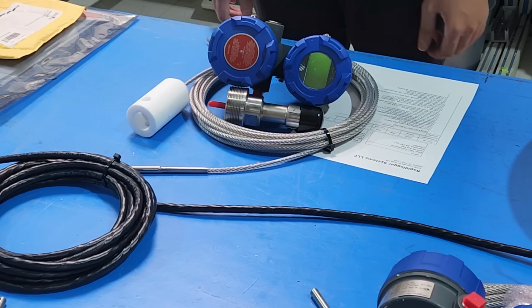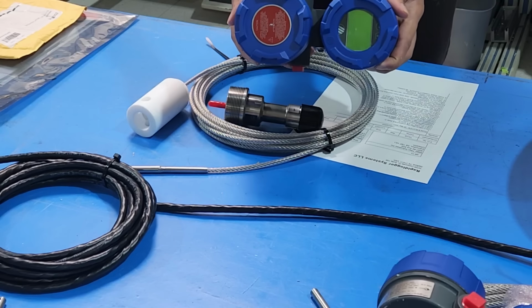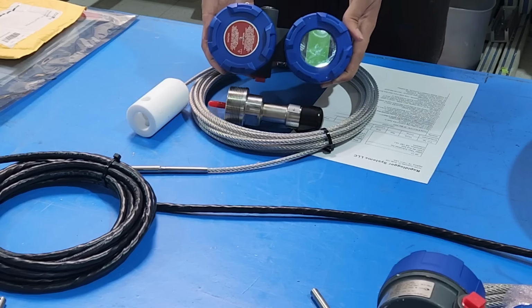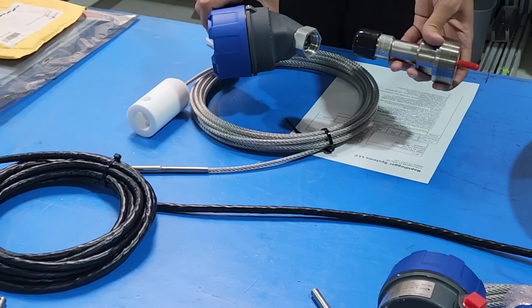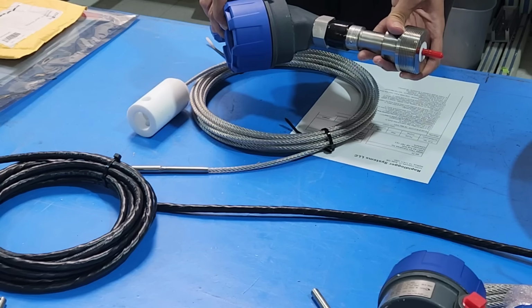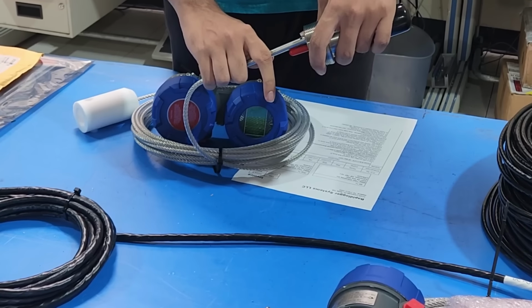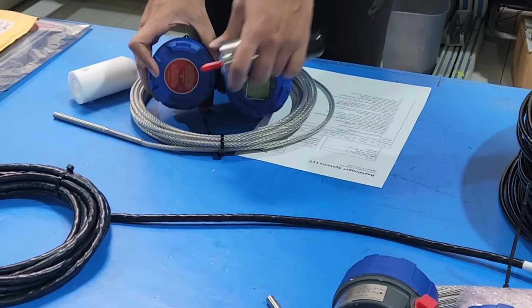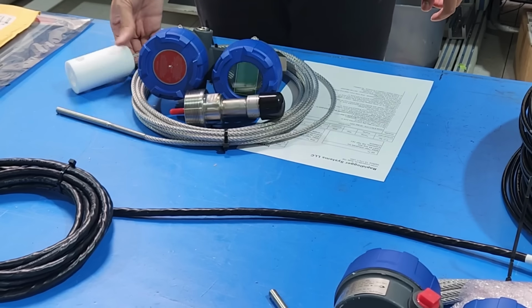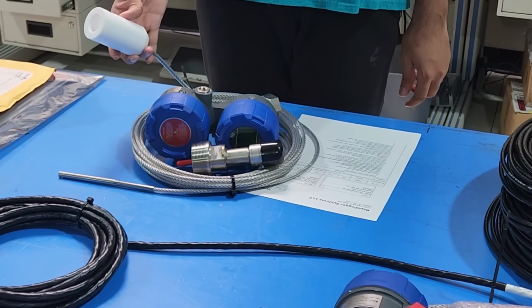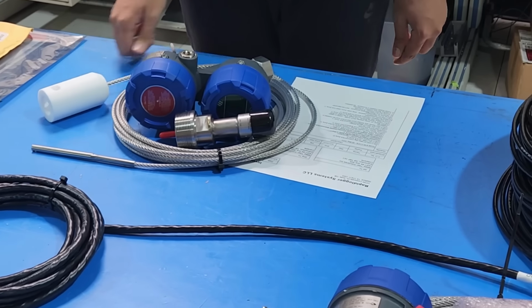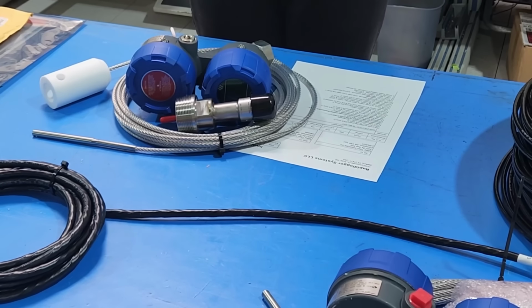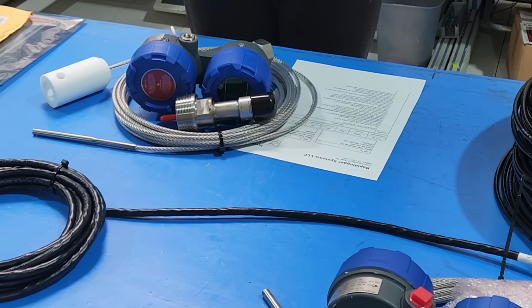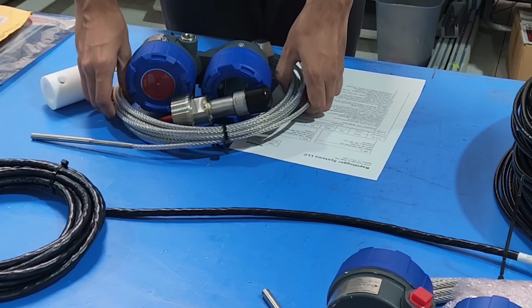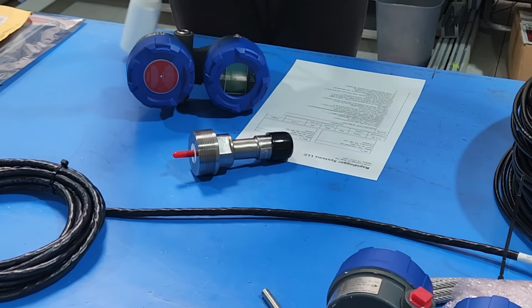The next sensor is the guided wave radar-based level sensor. This sensor is comprised of the main sensor body, the cable or wire rope adapter which connects to the back of the sensor, and the wire rope, which connects to the bottom of the wire rope adapter. The other end of the wire rope has a weighted anchor meant to be tied down at the bottom of a mud pit. The level sensor is used to measure the level of fluid, such as brine, mud, or oil, etc., in a tank or pit. It comes with a 25-foot wire rope for measuring level. This must be cut or tied off in the field to the appropriate length.